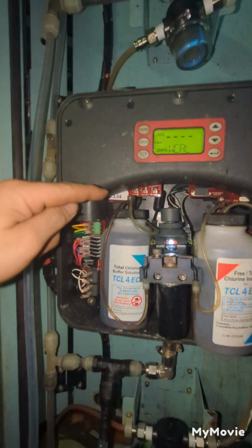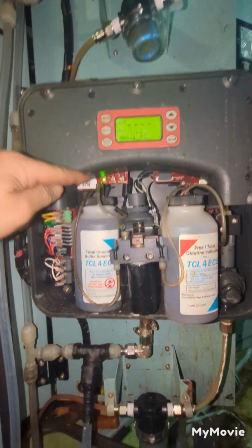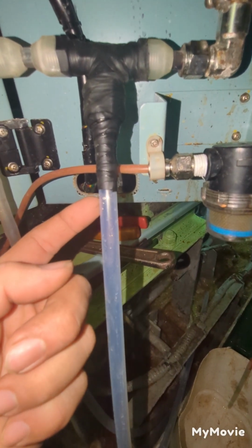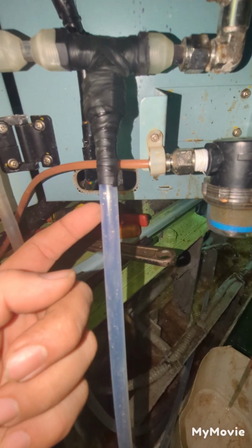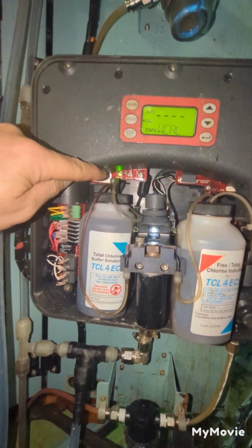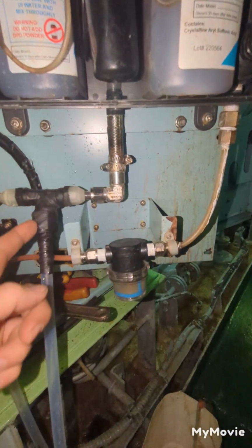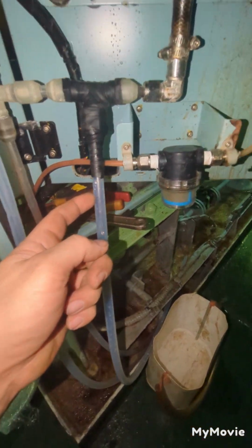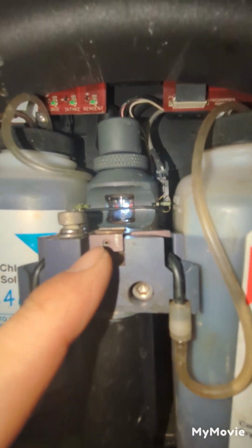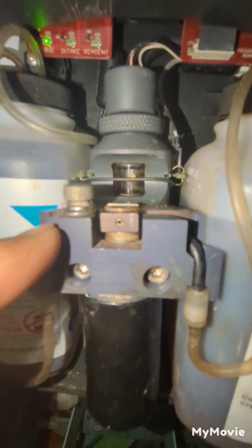Once the water is not enough, together with the total chlorine indicator and buffer solution, you have no good reading of a TRO value. So here is our drain during the purging period. Once the purging light is on, the sample water inside the cuvette glass will be discharged.